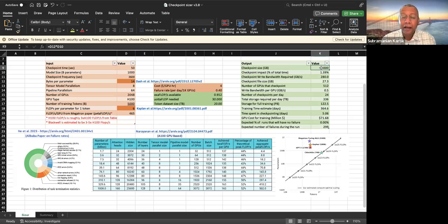So yeah, absolutely, we can calculate that, but it's frankly simple math. It's just take the number of GPUs, and remember, 8 GPUs is 10.4 kilowatts for the H100s. It's closer to 14.5 kilowatts for the Blackwells. And then you have your number. It's just simple math. Okay. And whatever comes in must go out, therefore the rest is heat.